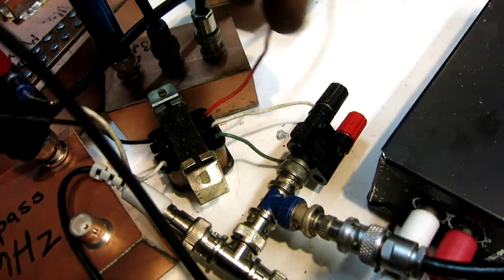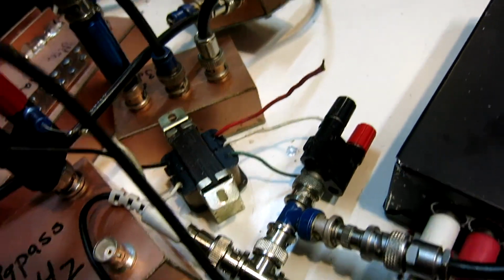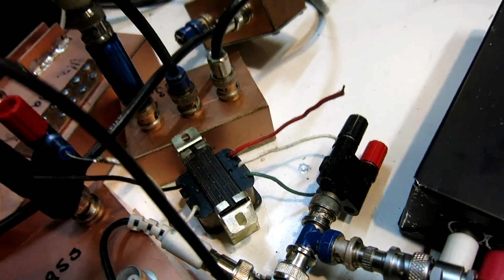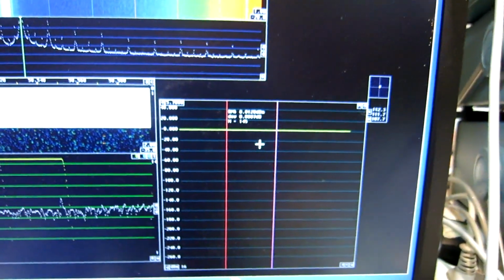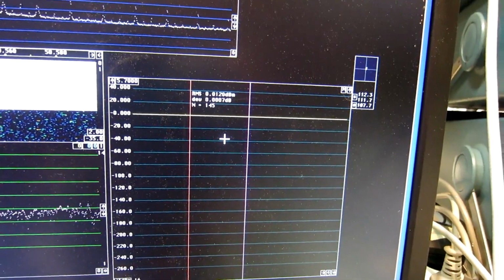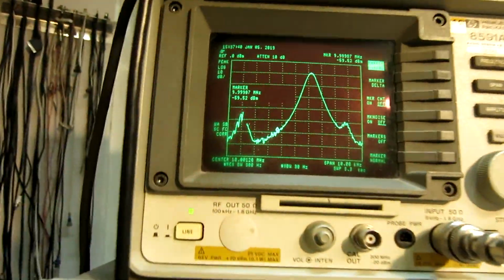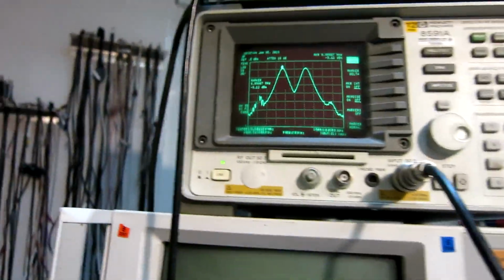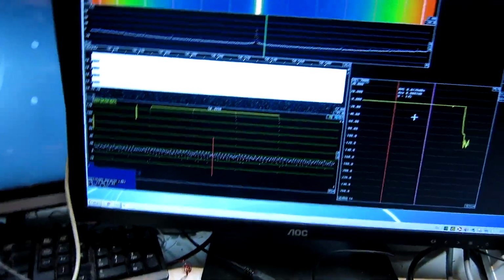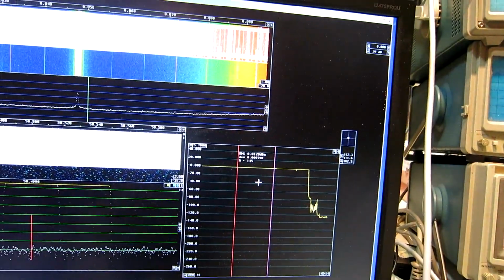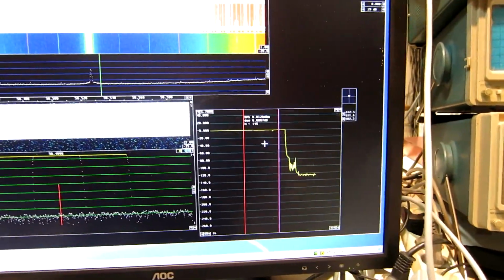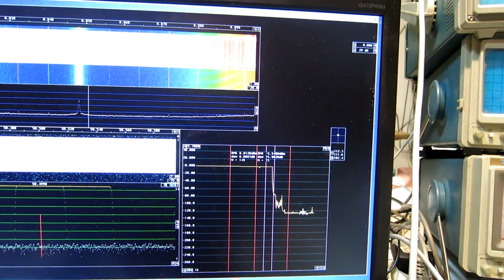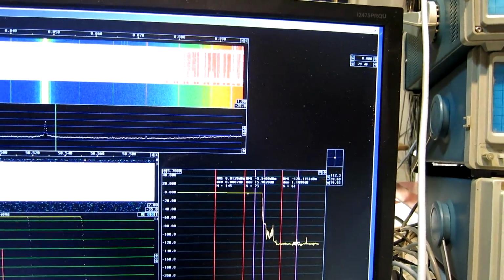As it turns out, this transformer had a far too high transformation ratio, so I use only half the secondary, and that gives a little bit more signal, and I have recalibrated it now to show 0 on the signal level of the signals I have. Now both signals are present, and I switch away the other one. Oops. And then I want to look at the noise floor again. And it's maybe a little better. Minus 126.